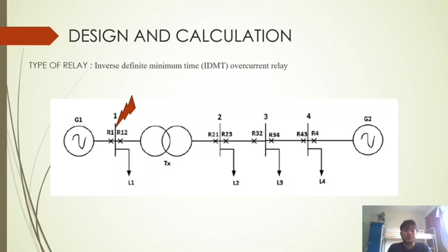So for the calculation, this is the rating set. The rating for generator 1 is equal to generator 2, which is 50 MVA. The setting is 100%. The time multiplier setting, TMS, is 0.3. The CT ratio is 800 per 5. The I fault is 1600 amperes, and the rated current is 5 amperes.